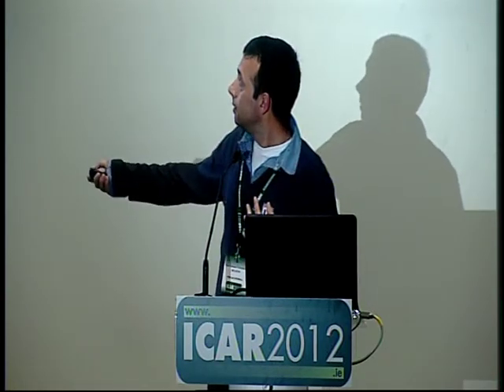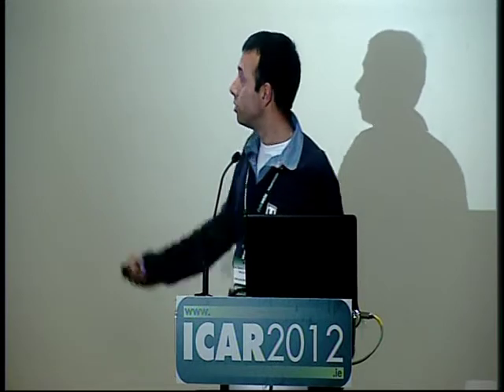The first thing that you can see is that the FOSS has 1,060 different wavelengths, so it's a long range. It's longer than the range measured by the Bentley, which is 889. Also, the FOSS is measuring transmittance, and the Bentley has been measuring absorbance, because the laboratory decided to do it like that, even if it was written in the protocol. But you have to take into account all these different things.